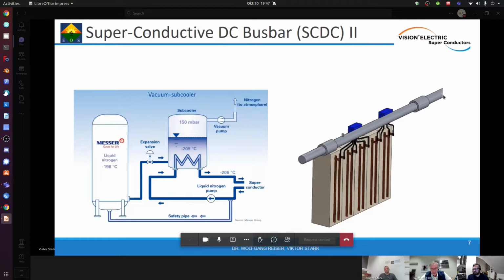The break-even point between supplying cooling power with liquid nitrogen versus using cooling machines is at about 10 cents per kilowatt hour in energy costs. That means if your energy cost at a data center is higher, liquid nitrogen supply is definitely much more efficient. And as you explained, liquid nitrogen is basically a waste product and relatively cost effective, right?